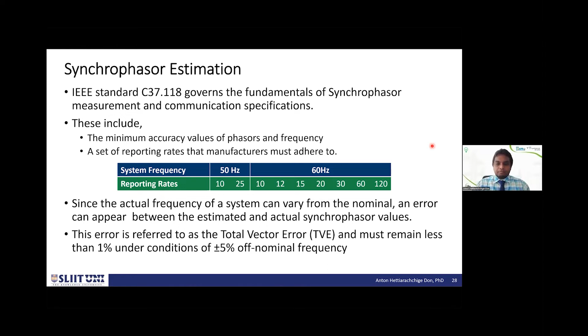According to the standard, you have to maintain what we call the total vector error. That means the total error as a phasor should be less than 1%, as long as the system is within 5% of the nominal frequency. So a manufacturer has to prove this before it is able to provide PMUs certified to the IEEE standard.